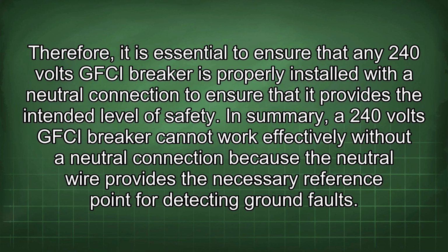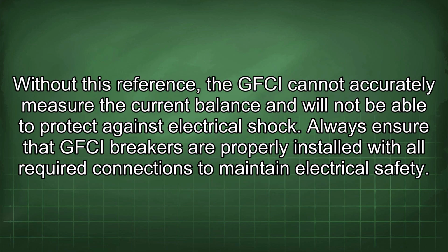In summary, a 240 volts GFCI breaker cannot work effectively without a neutral connection because the neutral wire provides the necessary reference point for detecting ground faults. Without this reference, the GFCI cannot accurately measure the current balance and will not be able to protect against electrical shock. Always ensure that GFCI breakers are properly installed with all required connections to maintain electrical safety.